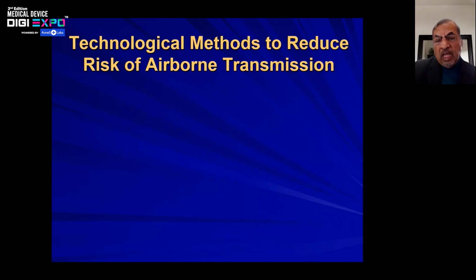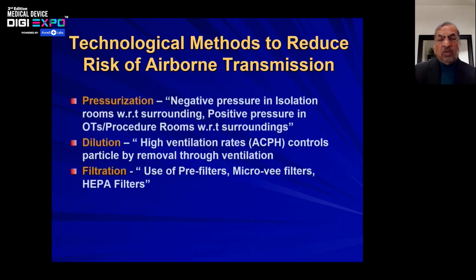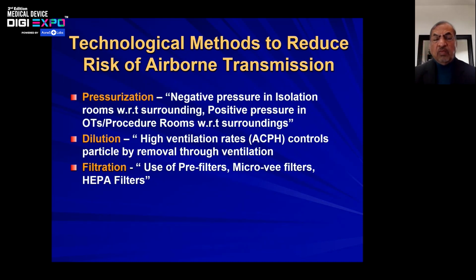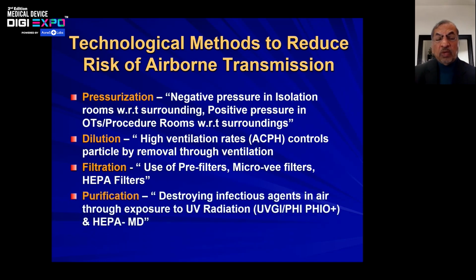Now I'll be talking about airborne transmission, the technologies we are using right now, which I spoke about in the initial stage. We use pressurization, that is negative pressure in an isolation room with respect to the surroundings, and positive pressure in OTs or procedure rooms with respect to the surroundings. Dilution means a high ventilation rate, air changes per hour, controlling particles by removal through ventilation. And the third one we used is filtration, using a pre-filter or micro-vee filter or HEPA filter.